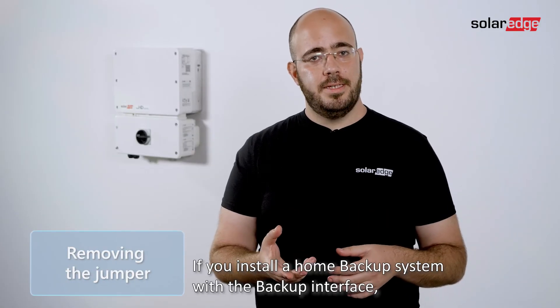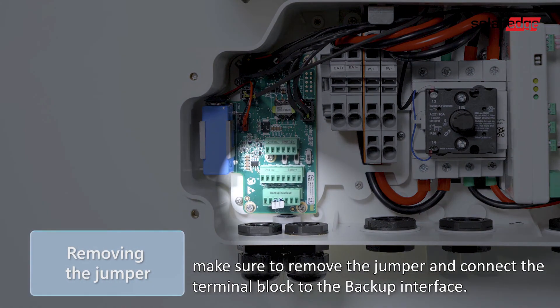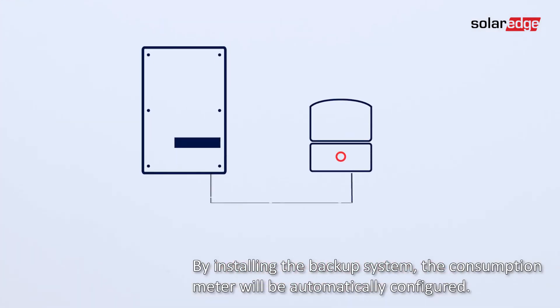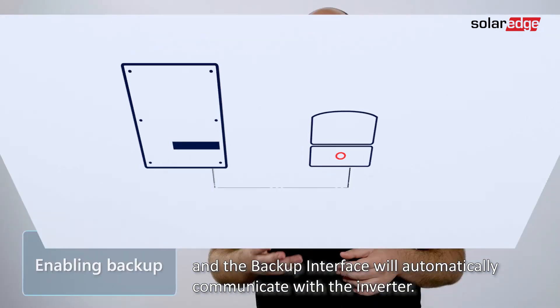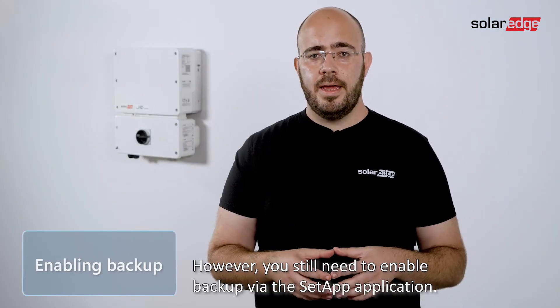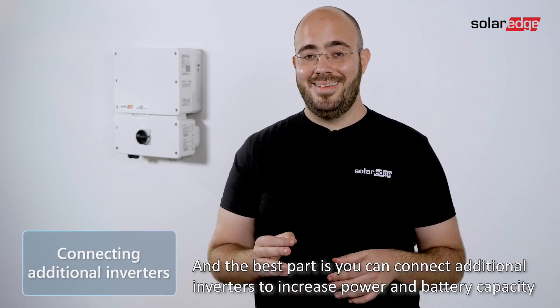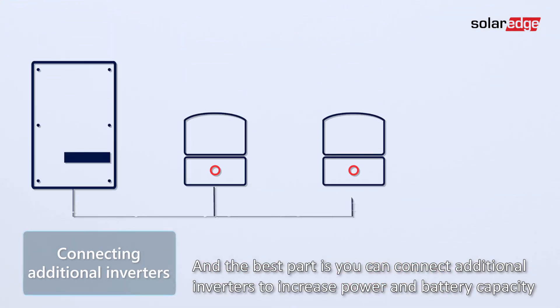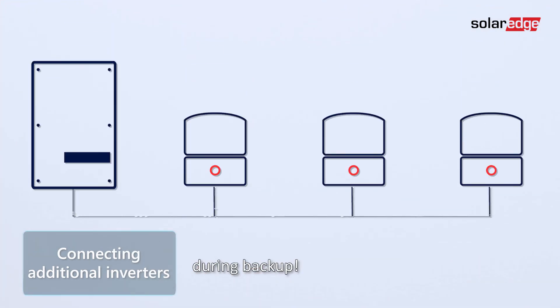If you install a home backup system with the backup interface, make sure to remove the jumper and connect the terminal block to the backup interface. By installing the backup interface, the consumption meter will be automatically configured and the backup interface will automatically communicate with the inverter. However, you still need to enable backup via the SetApp application. And the best part is, you can connect additional inverters to increase power and battery capacity during backup.